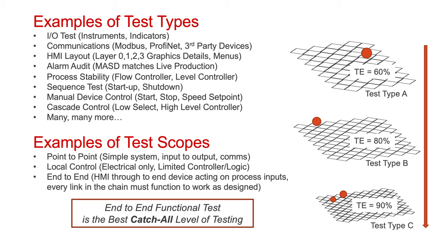Certain test scopes in automation are quite common. Point-to-point is often referred to for simple systems — input to output and checking comms, meaning the input on one side results in an output on the other. A point-to-point test with electrical wiring is also quite common. Local control tests are done generally in fields where we want to completely bypass the control system. Sometimes there are electrical switches that bypass the output run command from a controller, and in those cases we do a local control test where the local manual push button directly drives the device in question. The more interesting one is the end-to-end — all layers in the stack, everything from the HMI all the way down through to the end device acting on the process inputs. Every single link in the chain must function, otherwise the result will not work as designed.